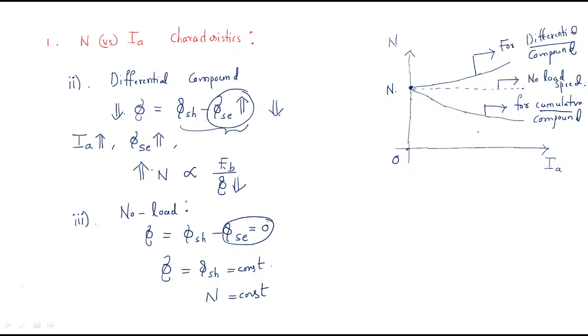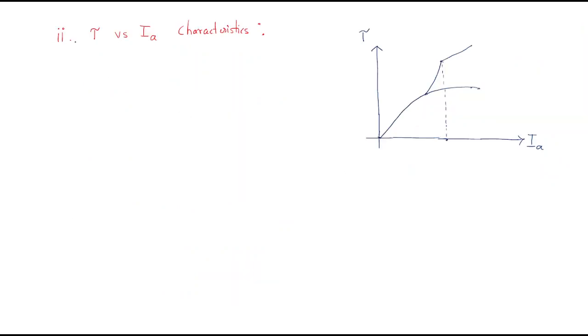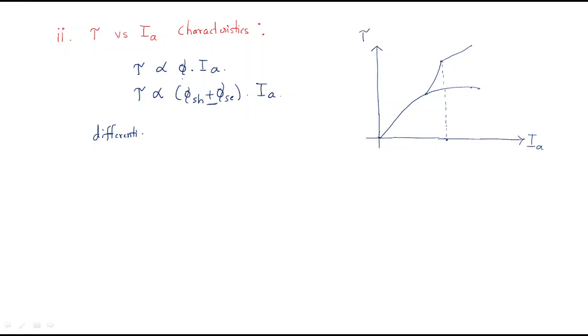Next are the torque vs. armature current characteristics. Generally for any DC machine, torque is proportional to flux times armature current. For a compound motor, the flux is a combination of shunt flux and series flux. In the case of differential compound, the total flux decreases, so the torque also decreases after a certain point.